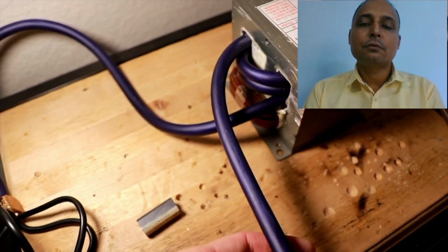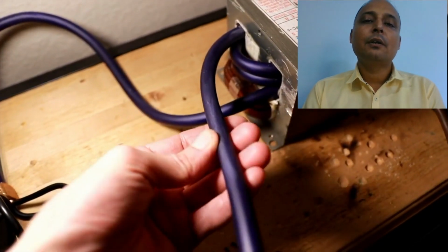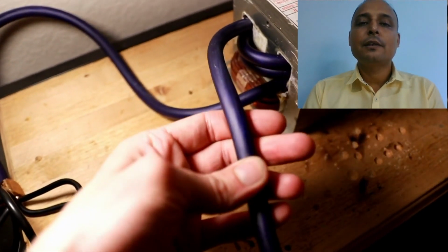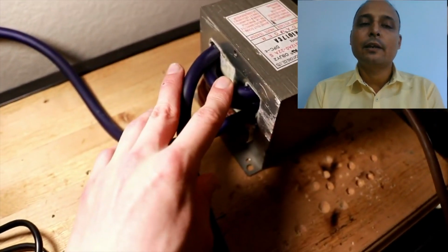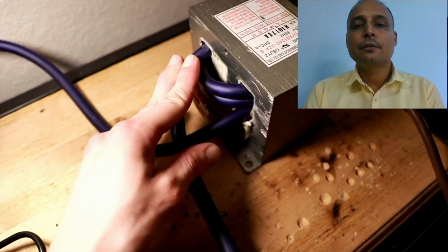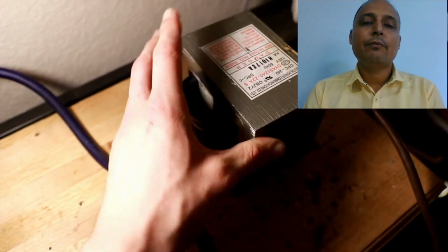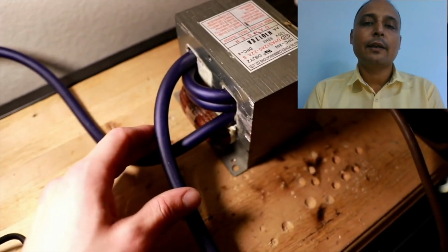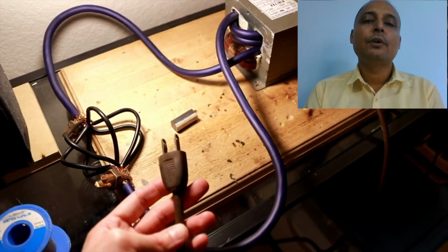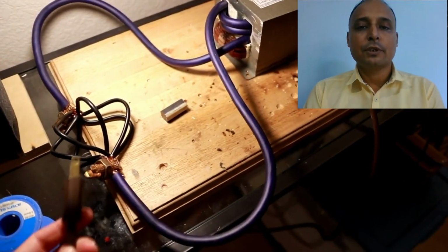We are also showing here the current that is flowing through the secondary side using a clamp meter, and it shows a very high current that flows through the secondary side of each phase, and therefore this is a very high amount of current that is actually flowing through the secondary side of the transformer.